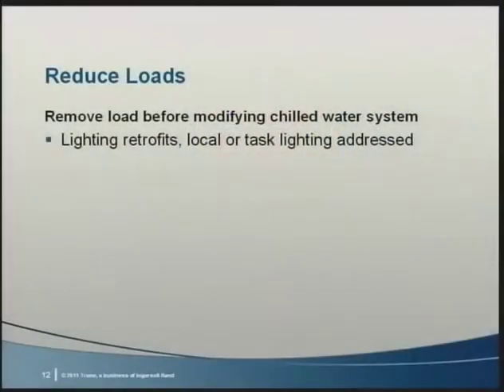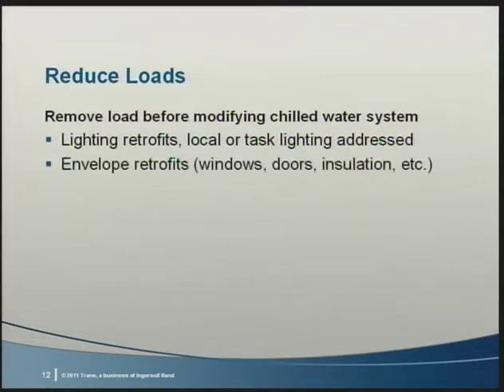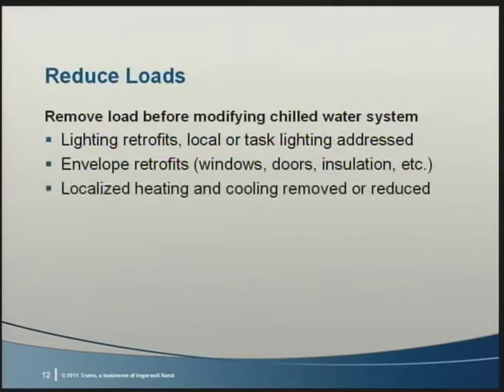Take a hard look at the rest of the building beforehand. Reduce loads. It's no surprise to anyone that lighting and envelope improvements save a bunch of money. Lighting retrofits save energy twice when spaces are being cooled, but their improved efficiency may add to space heating requirements. On the flip side, envelope improvements save especially on heating. When you take a look at your spaces, how many under-desk heaters or fans do you see? An energy audit can identify those items and also tell you a lot about what the deficiencies are in your building. So let's talk about reducing loads in a meaningful way.